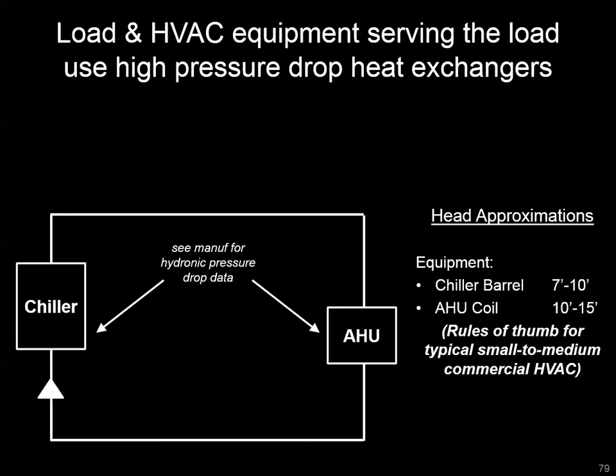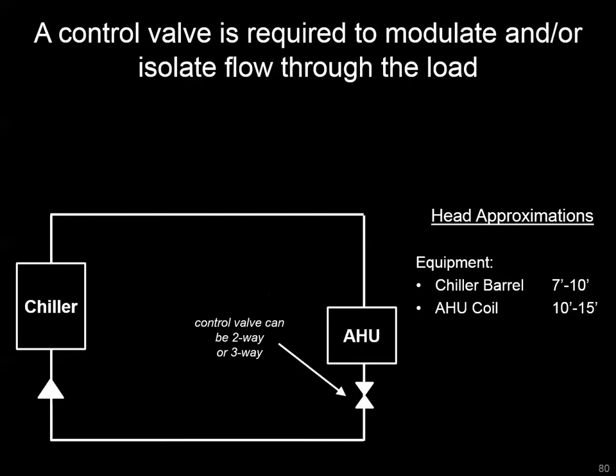Seven to ten feet for a typical commercial HVAC chiller barrel might be in the right neighborhood. Air handler coil, ten to fifteen feet depending on size. Those are good places to start.